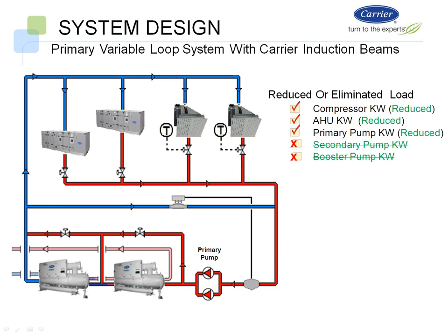So let alone the fact that if you have a wheel in there and assume a certain static pressure drop, that's just adding more brake horsepower to the air system that's delivering the primary air. So in essence, we should be more efficient too, because we're not going to have the added static pressure drop through the loss of the one or two wheels. Correct. Especially with the dual wheels that I've seen out there. There's a lot to consider there. So that's why I'm saying you're getting right down to a standard type air handling unit versus anything custom or even semi-custom. So that's some of the benefits of using this type of beam and how it can apply to both your air side and your water side.